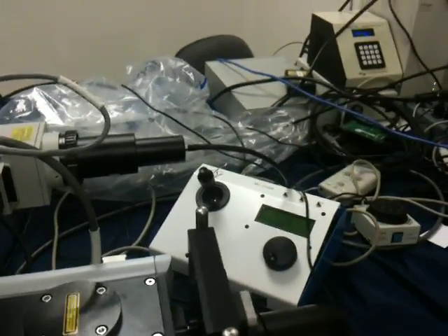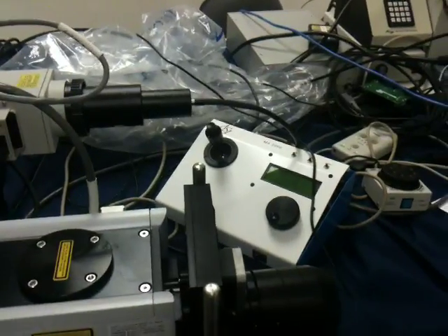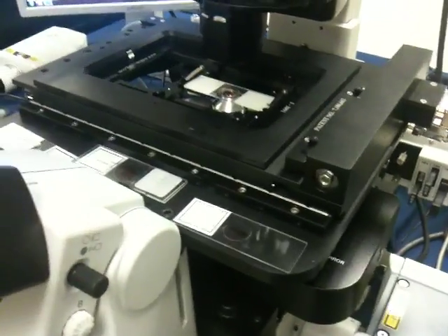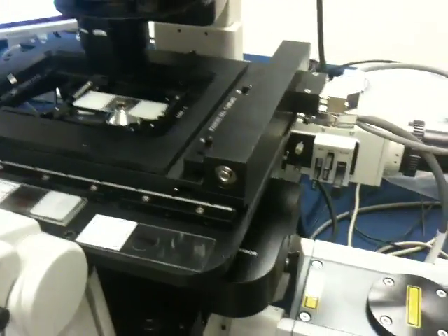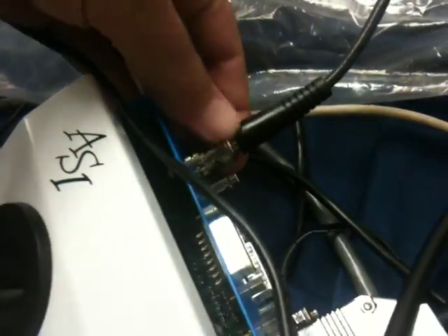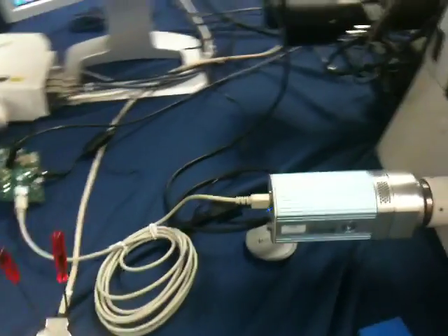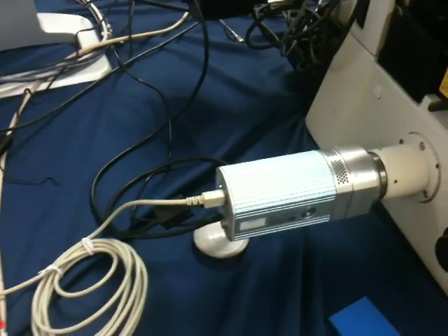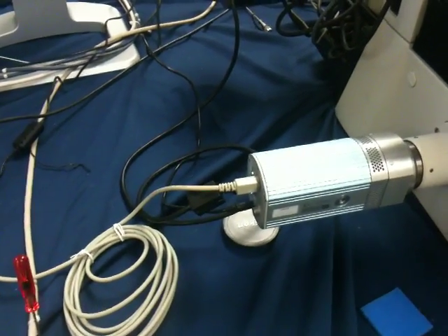So I've set up the ASI controller with a code string. Basically all it's doing at this point is waiting for the TTL signal. Of course, we can do a full closed loop system. There are two connections on the ASI, input and output. So in the lower position here we could do, and probably should do for this type of setup, a "don't take a picture until the stage has stopped moving" kind of command.